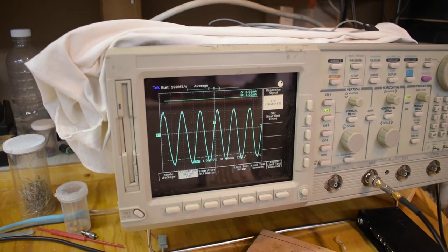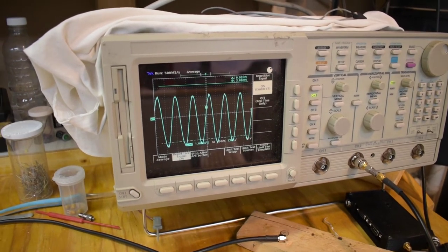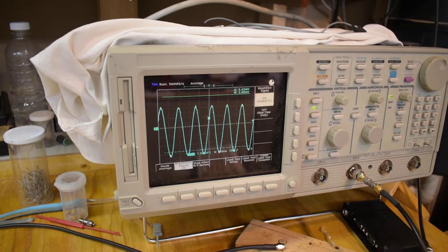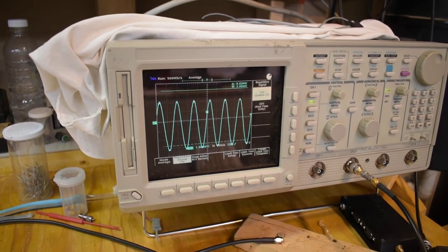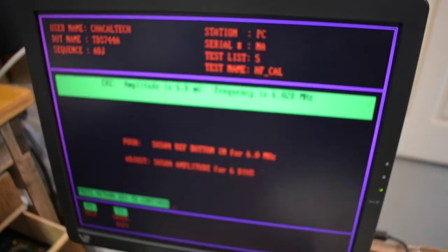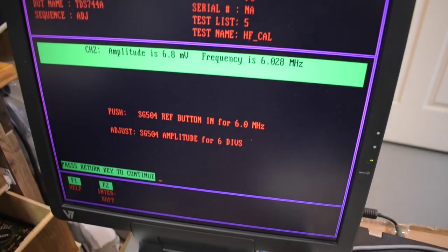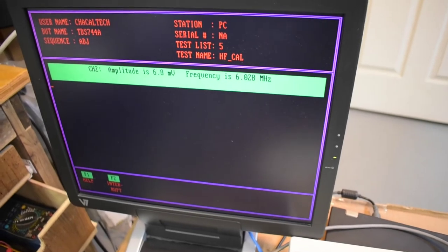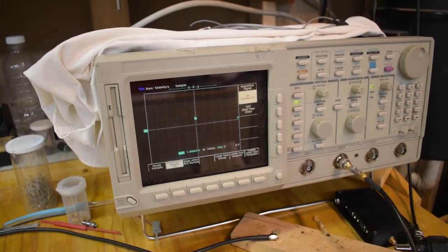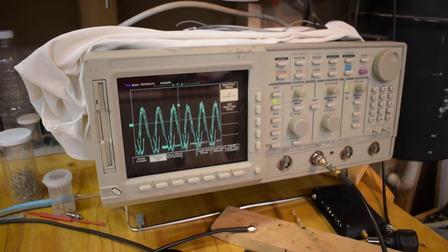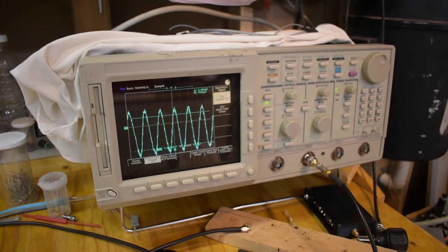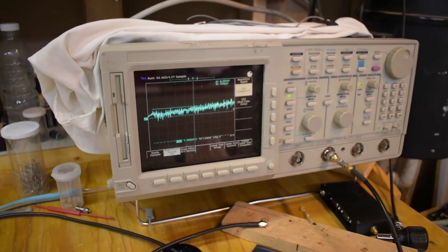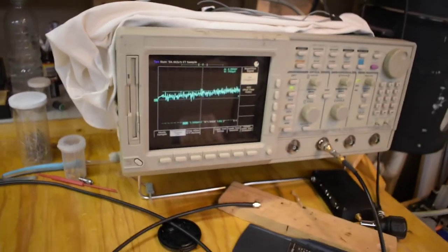Okay, for example, this is the worst. 1 millivolt per div. It sets those cursors there. I set roughly what I thought was a good amplitude. There's a bit of an offset. So it tells me amplitude is 6.8, frequency 6, and so on. It tells me try again, basically. So I just tweaked the amplitude a bit. I think this is going to be better. Let me see. Press enter. Does a couple of things there. Perfect. So it readjusted the cursors, see? To take into account the offset of my generator, which is a pretty nice thing to do for me.